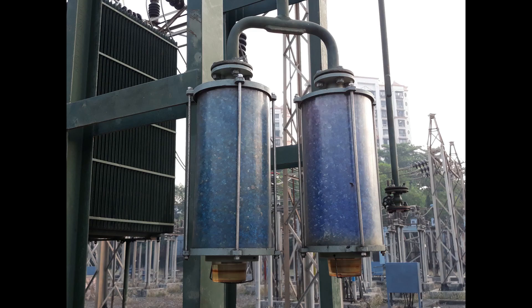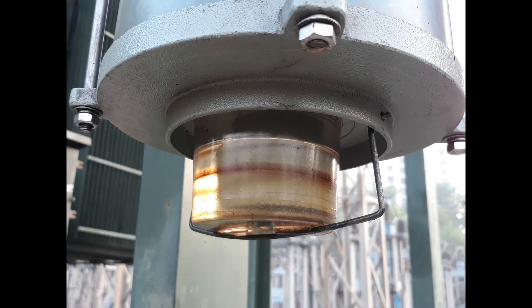Here please note that air which gets inside the air cell passes through silica gel breathers. This silica has the property of absorbing water. Also, there is an oil cap at the bottom of the breather which catches any other contaminations in the air. Hence the air that goes in the air cell is dry and free of contamination.